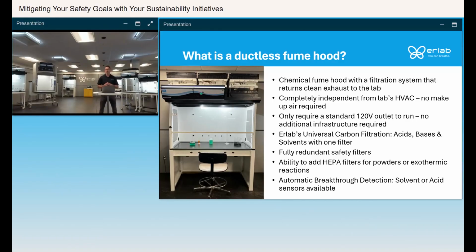With a ductless fume hood, you remove all that infrastructure, all that ductwork, and instead you use an advanced carbon filtration system to capture the chemical vapors and fumes that are generated within the enclosure and return clean air to the lab. That means you don't need to integrate it to your HVAC. You don't need to balance the air. You don't need makeup air. They're very simple to add to your lab. All you need is space and a 120-volt outlet. And what makes Erlab's carbon filtration different than everybody else is that we have universal carbon filtration.